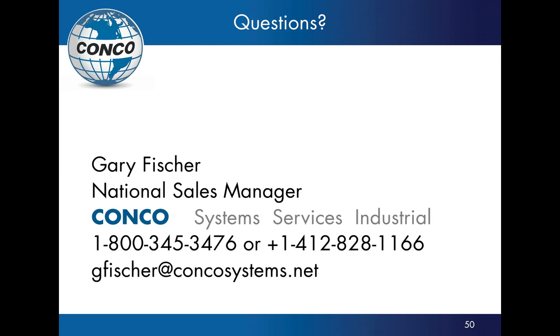And how often is it recommended to perform these eddy current tests? Okay, what we recommend is when you have your unit up and running, if you have not done a complete test, we recommend that you do a complete test of 100% of your tubes to get a baseline. Then, depending on the test results, you should do in increments of 10, 15, 20% every year. And if you do 10% on a new condenser over a 10-year period, you will have tested every tube once.